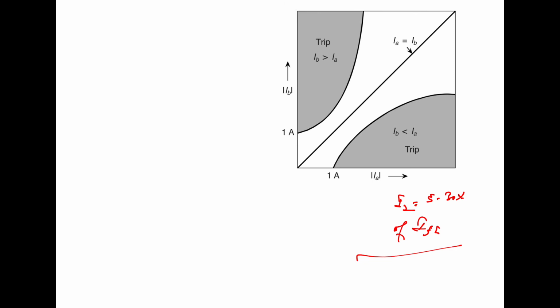Now, here we have the characteristics of the relay for detecting the imbalance. The relay consists of two units. One unit balances IA against IB, while the other unit balances IB against IC. When the currents become sufficiently unbalanced, the torque developed in one or both of the units causes the relay to trip. Now in this case, the current is balanced, so there is no need to trip. However, when IB is less than IA or IB is greater than IA, it will definitely give the trip circuit signal. So this is used for this explanation.